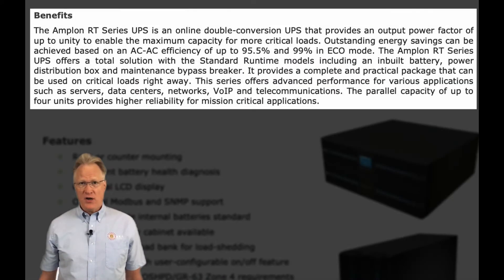The Amplon RT Series UPS is a single-phase, online, double conversion UPS that provides an output power factor of up to unity. AC to AC efficiency is over 95% during normal operation, and almost 99% in economy mode. Each unit has an internal battery, a power distribution section, and a maintenance bypass breaker.